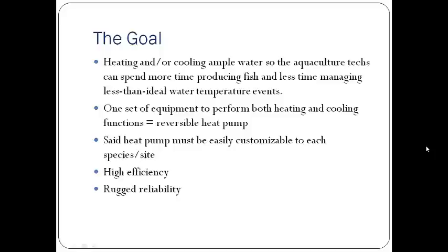Another benefit of the heat pump would be to have one piece of equipment that could heat the water and cool the water, rather than the more common application of maybe oil-fired boilers to heat, air-cooled chillers to cool in the summer. Simply with the heat pump, less capital cost, less maintenance cost on one piece of equipment, less footprint required, and so on. So this heat pump would also have to be easily customizable to go from one species to another, one site to another. High efficiency is a must, and reliability is clearly something that has to be focused on in this application.